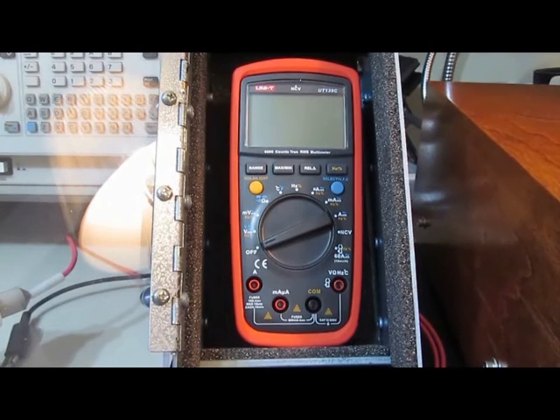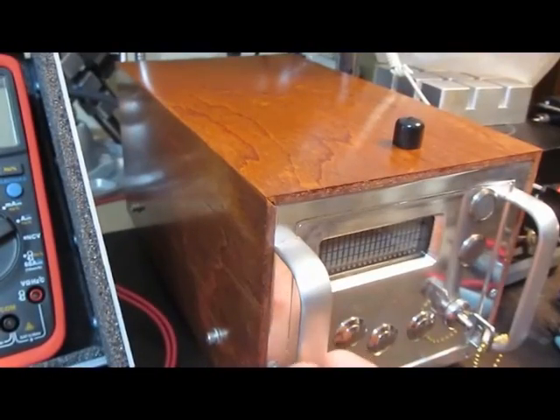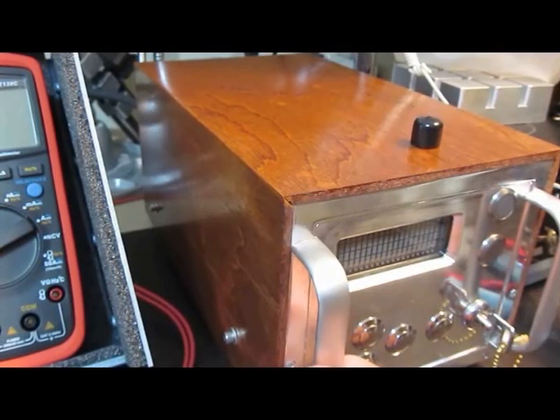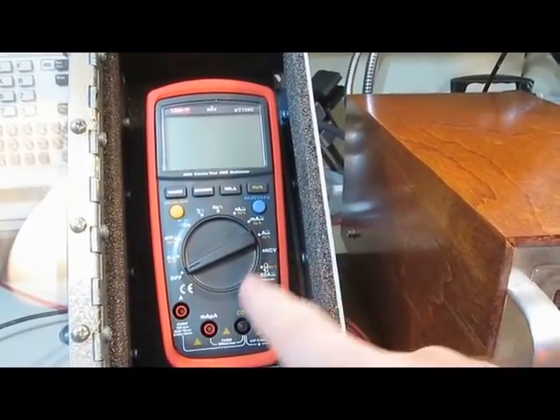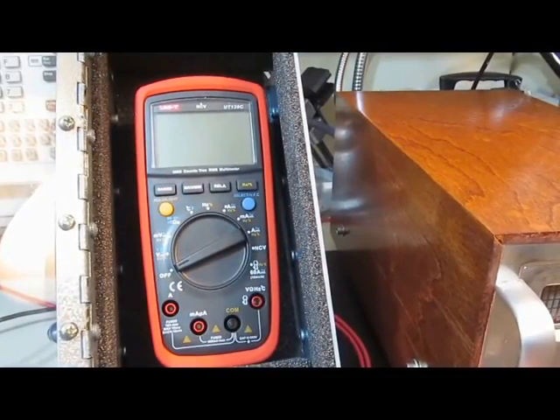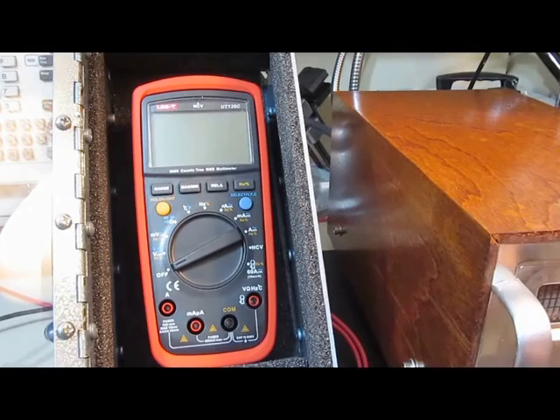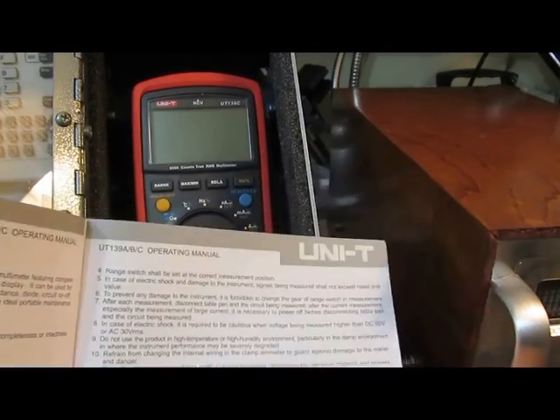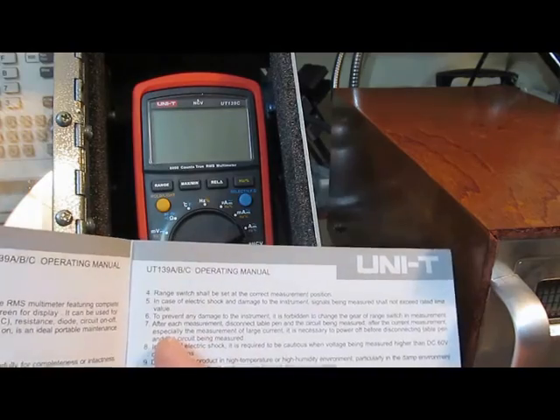So again, this transient generator has a step-up transformer, so I'll take the 110 volt line voltage that we use here, and we'll step that up to 220, but then I rectify the signal, and that's what I actually put into the meters. So this is a rectified DC signal. I limit the current. The max the transformer is good for is about 500 milliamps, but I lower it even further with the box itself. So the box is monitoring the current, and if the meter draws an excessive amount, it'll just shut down the output.